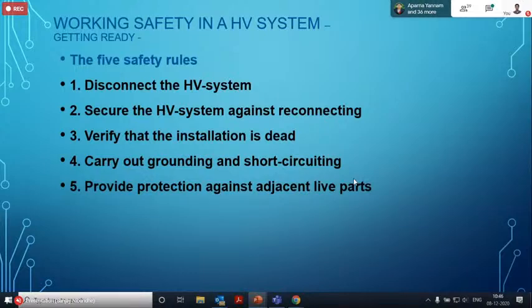Disconnect HV systems, secure HV systems against reconnecting, then verify that the installation is dead. Without that, you will not open the systems. Carry out grounding and short circuiting. One has to be very sure that proper grounding has been taken care of.